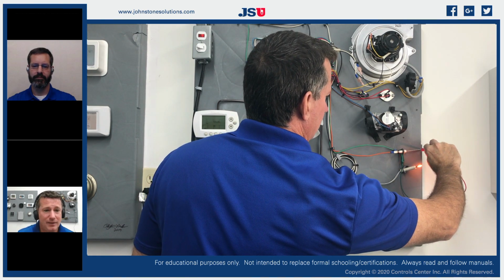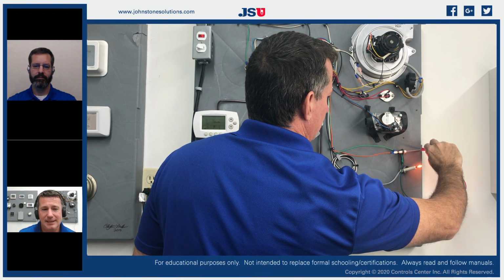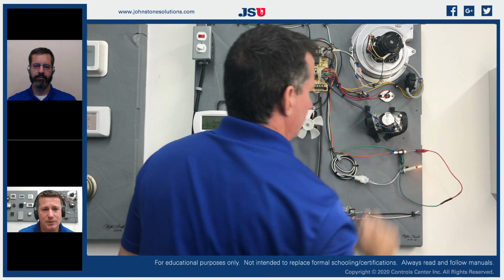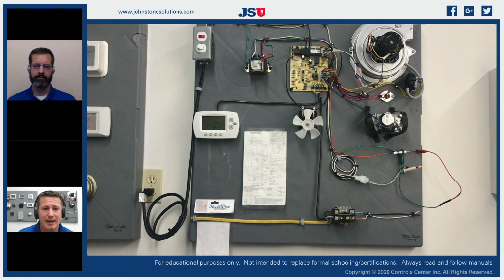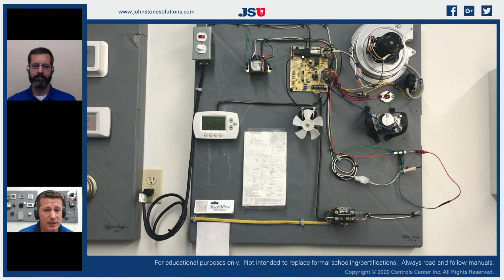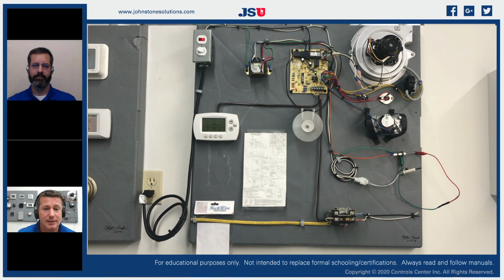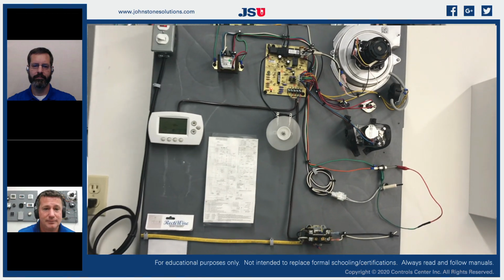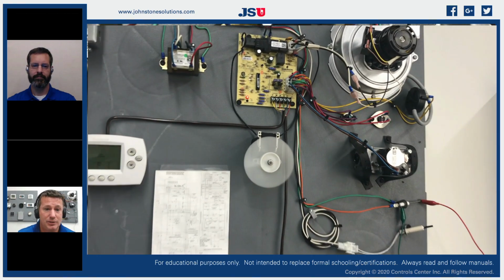After ignition of the hot surface igniter, in the safety time period after my gas valve comes on, I immediately apply my rectification circuit, which is a 1.5 microamp DC load from ground to the tip of the flame rod. And I have a happy circuit board. I just brought on my fan and I have no error codes.